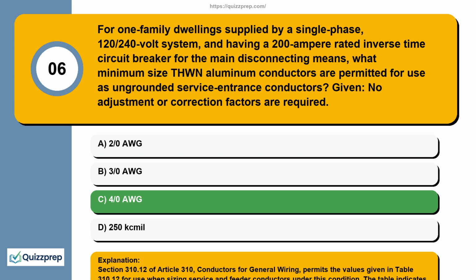Section 310.12 of Article 310, Conductors for General Wiring, permits the values given in Table 310.12 for use when sizing service and feeder conductors under this condition. The table indicates size 4/0 AWG aluminum conductors are the smallest size permitted for a 200 ampere rated service if no adjustment or correction factors are applied.